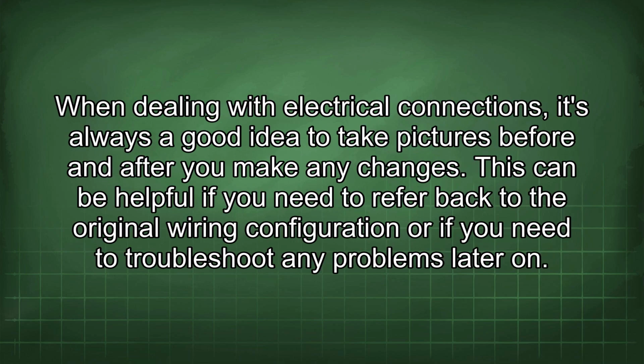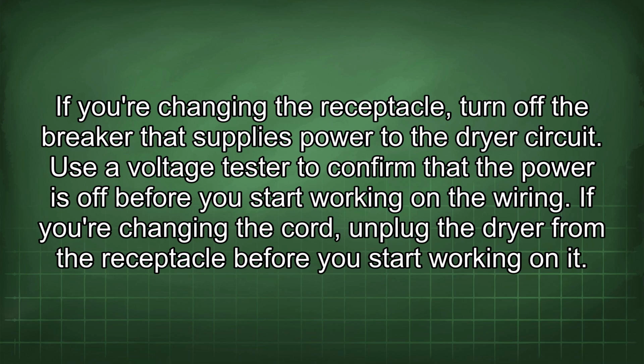When dealing with electrical connections, it's always a good idea to take pictures before and after you make any changes. This can be helpful if you need to refer back to the original wiring configuration or if you need to troubleshoot any problems later on. If you're changing the receptacle, turn off the breaker that supplies power to the dryer circuit. Use a voltage tester to confirm that the power is off before you start working on the wiring. If you're changing the cord, unplug the dryer from the receptacle before you start working on it.